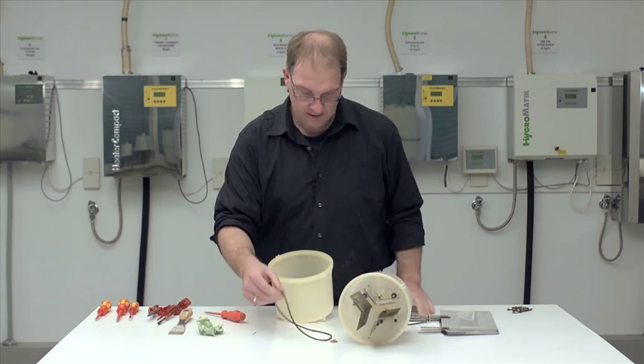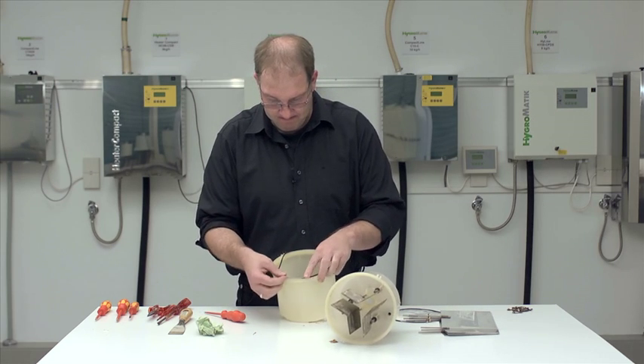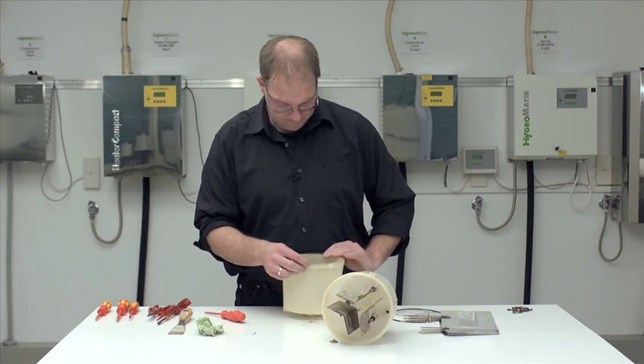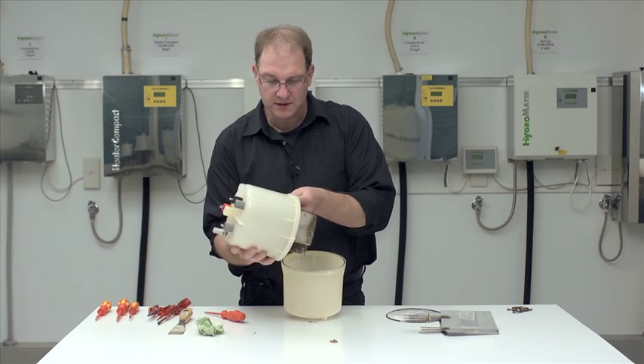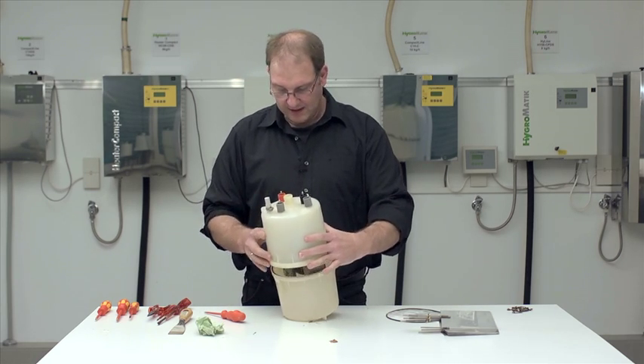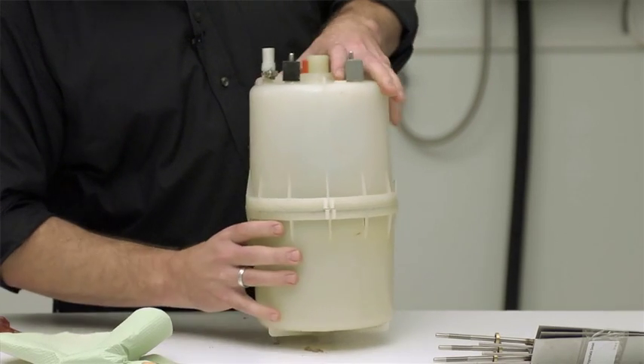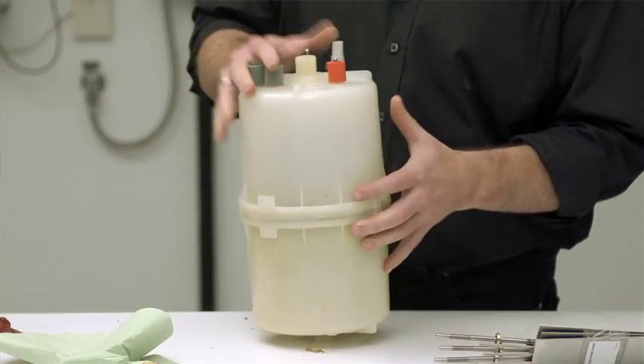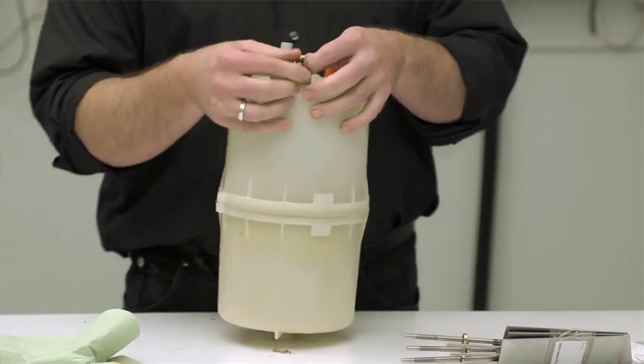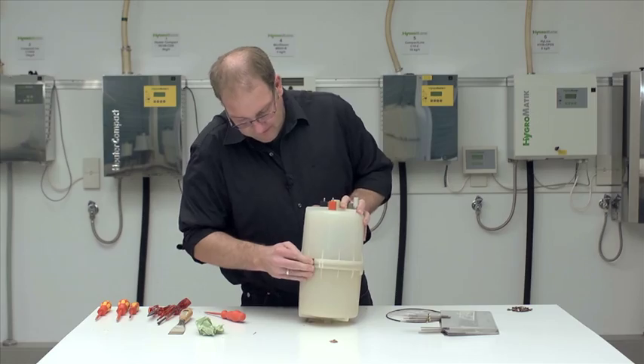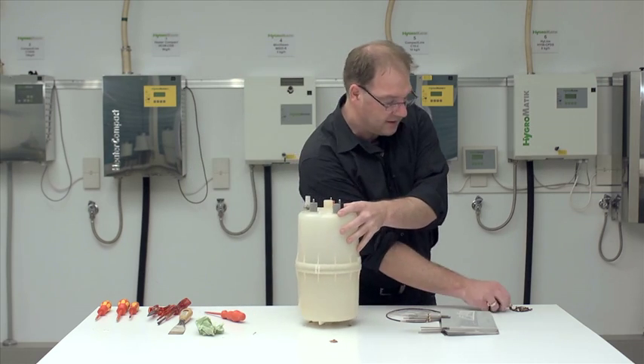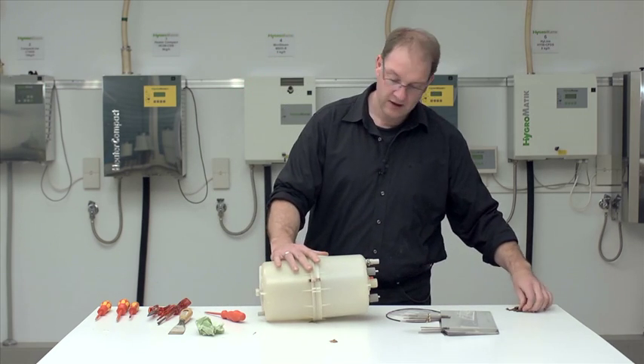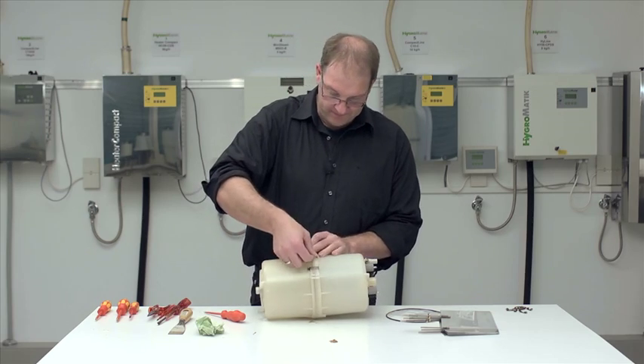Now, the new o-ring is inserted there, and I can reconnect the top and bottom sections. When you are placing the two parts together, please make sure the joints and reinforcements are aligned here and there, then they are in the proper position and fit together snugly. I'm going to secure the position with the first clamp, I'll press it on here, and then take the direct opposite side and apply the next clamp. I can then conveniently place the whole cylinder onto the table and apply clamp after clamp.